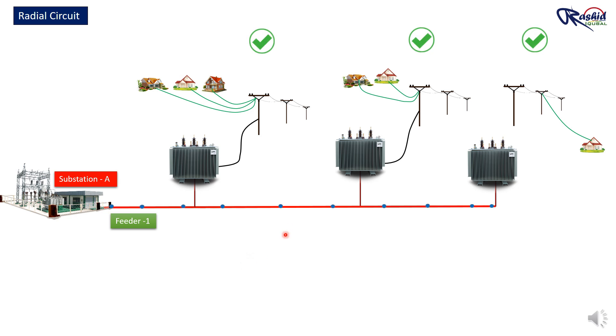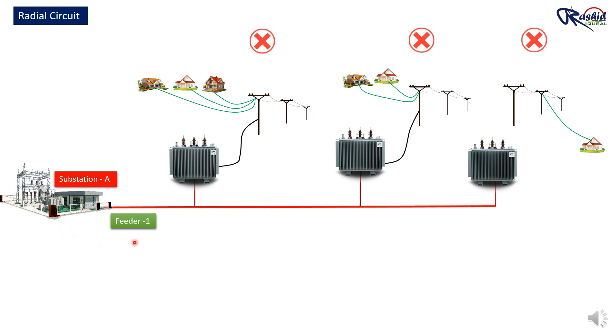However, if there is a fault or cable damage anywhere along this feeder, the entire system will be affected. When a fault occurs, the circuit breaker at the substation will automatically trip to protect the system. As a result, power to all the transformers connected to this feeder will be cut off, leading to a blackout for all the consumers in that area.